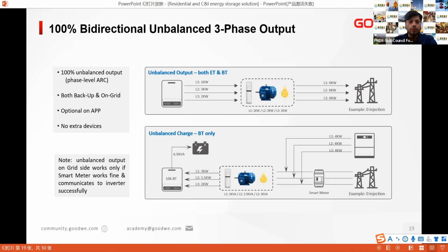So in this condition, the shortfall power could be taken from the grid, that is what you mean by this unbalanced output. What I was assuming is that normally in a hybrid or complete off-grid system, when you connect the load on three phases and it is unbalanced, the system normally has an issue. If it is more than 50% unbalanced, suppose for a 30 kilowatt system, one phase has 5 kilowatt connected and the other two phases have 15 or 20 kilowatt, then normally the inverter gets tripped. So that is the unbalancing of the load issue for this off-grid system.